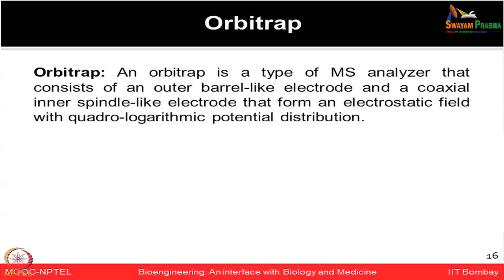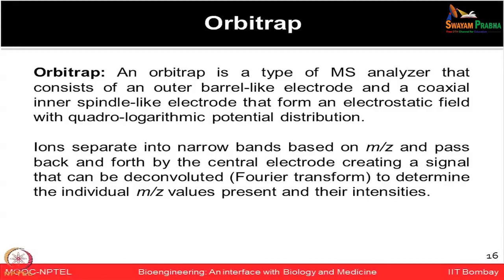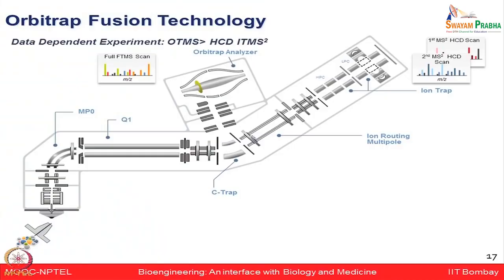The Orbitrap is a type of mass analyzer consisting of an outer barrel-like electrode and a coaxial inner spindle-like electrode that form an electrostatic field with quadro-logarithmic potential distribution. Ions separate into narrow bands based on mass-to-charge ratio, passing back and forth by the central electrode, creating a signal that can be deconvoluted to determine individual mass-to-charge values and their intensities. The Orbitrap Fusion tribrid technology combines quadrupoles, ion traps, and Orbitraps—each with their own detectors—providing highest resolution and multiple fragmentation capabilities for diverse applications.